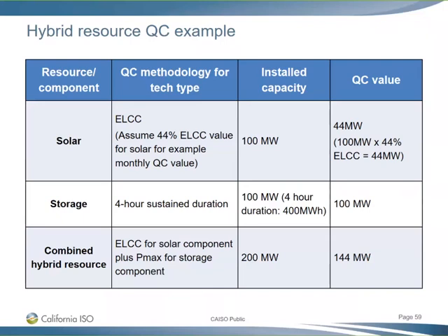On this slide, before we go to the phone, we provided a simplified numerical example of that proposal from the previous slide. If you combine solar and storage, assuming a 44% ELCC value for the month and a 100-megawatt facility, that would be worth 44 megawatts of ELCC. A 4-hour sustained duration 100-megawatt, 400-megawatt-hour battery would be 100 megawatts of QC, and adding those together gives you 144 megawatt QC. We just wanted to provide that as an example included in the proposal.